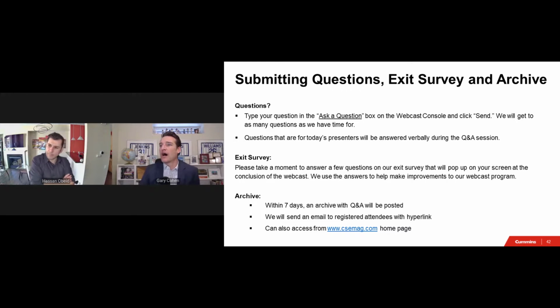Got it. Can you apply the integrated paralleling to medium voltage systems? Yes, it can. So it's not just for 480 or 600 volts. We don't care if it's a 4160, 13.8 or higher. That's the power aspect, right? The controllers are independent. They're just doing the synchronization using the zeros and ones, and using a lower voltage to do that. The power sections are independent of the paralleling.